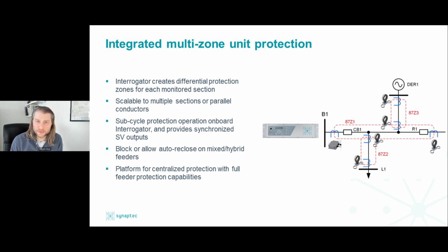And some of the things that Bogdan's already hinted about, we can add some extra provisions here relatively easily to help counter wildfire-specific events. So high impedance fault detection and open circuit protection can play a part here in helping with wildfire prevention. And that becomes significantly easier compared to just making decisions based on substation measurements, where you're restricted to what you can see. This approach can also help to optimize autoreclose on circuits which have a mixture of conductor types. Obviously you want to block reclosing for cable faults or in scenarios where there's maybe a high risk of wildfire, so having that capability to discriminate between cables and overhead lines can be very useful.